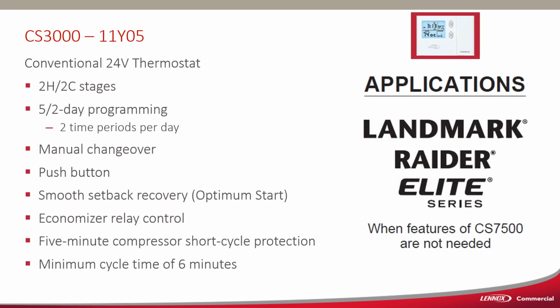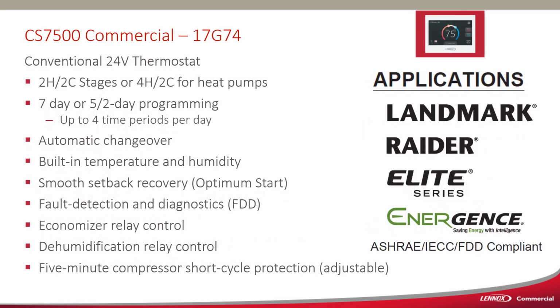We also have a ComfortSense 3000. This is our down and dirty thermostat. Typically, you'd use it on the Landmark, Raider, or the Elite series split systems. 2-stage heat, 2-stage cool, 5-day programmable with 2 periods per day. That's a manual changeover, push button. It's not a touchscreen, it's push button. It does have smooth setback recovery. It also has, of course, to be commercial, an economizer relay control and a 5-minute compressor short cycle protection and a minimum cycle time of 6 minutes.